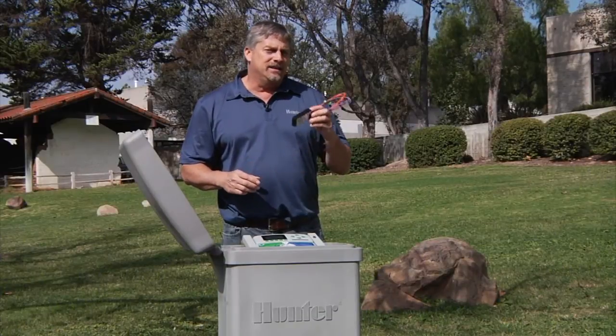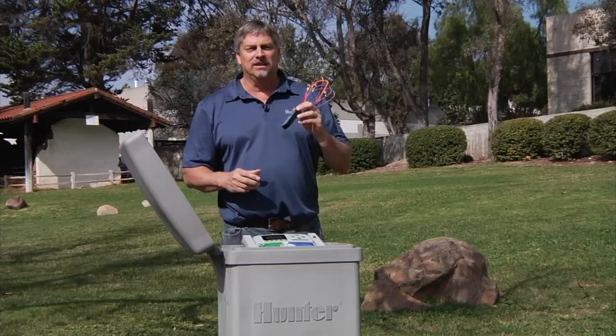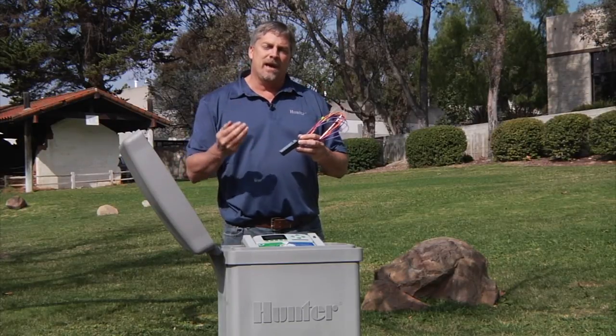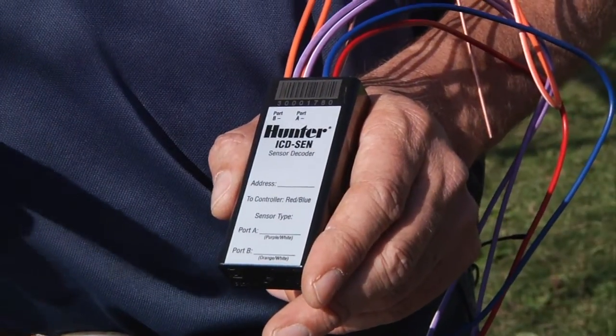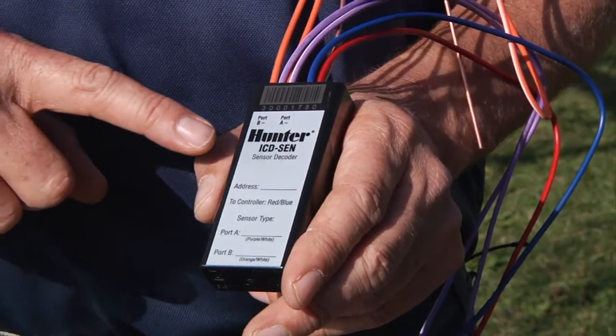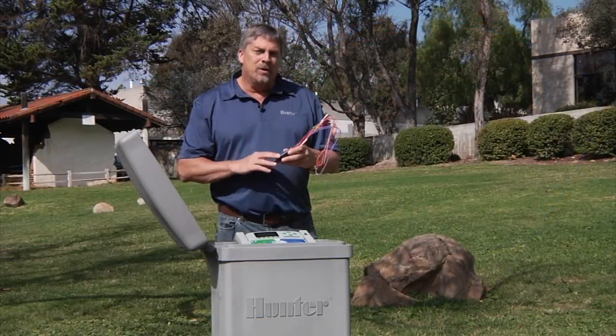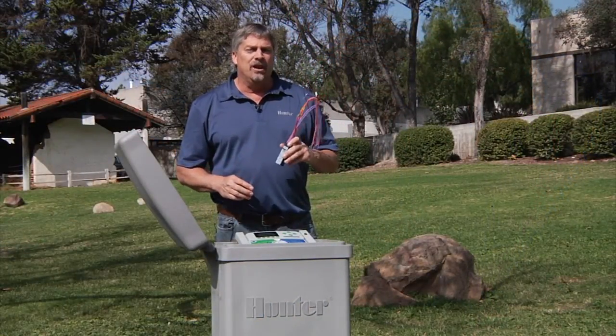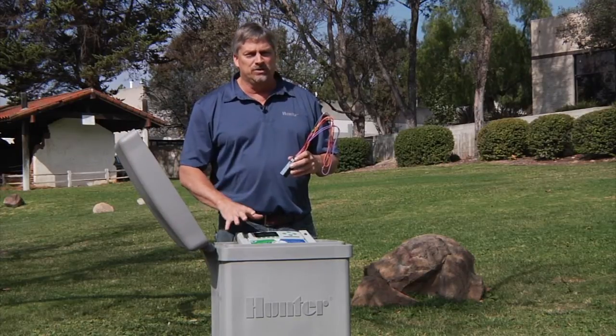The ACC-99D allows you to connect a flow sensor or any normally closed click-style sensor through a decoder on the two-wire path back to the controller. To connect a sensor through a decoder, you must use a sensor decoder, also known as ICD-SEN. Before programming and installing a sensor decoder, there are some selections that need to be made in the controller based on what type of sensor you'll be using.